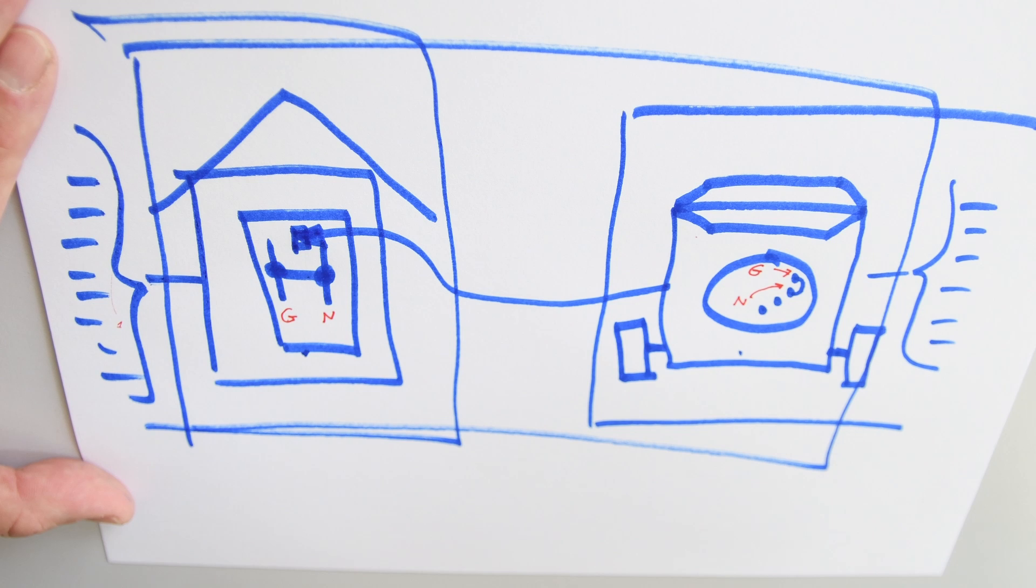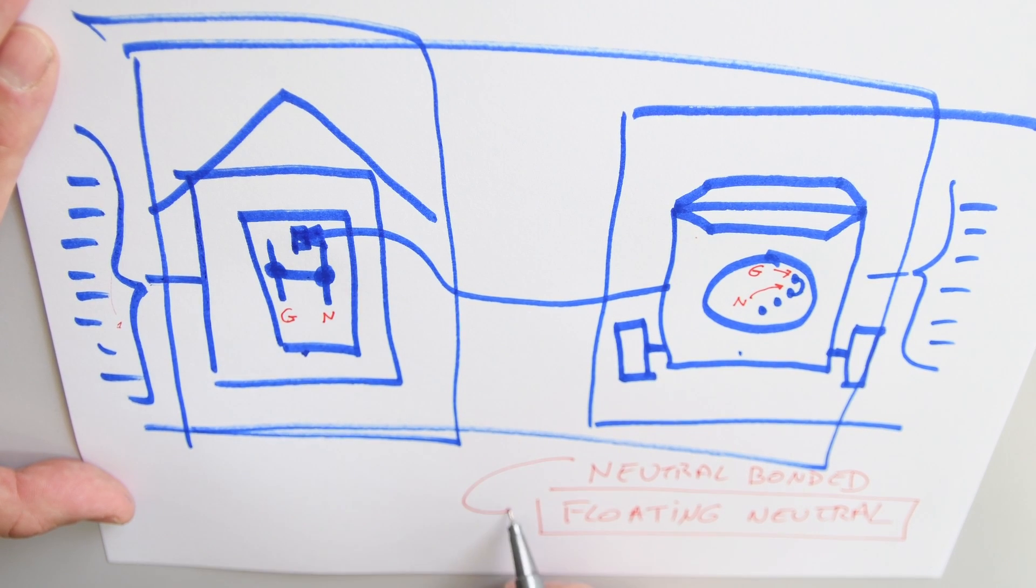By doing so, we'll turn what is called a neutral bonded generator, which is the way they come for the most part when you buy new, and we'll convert it to a floating neutral. So this is the conversion we're going to do next.